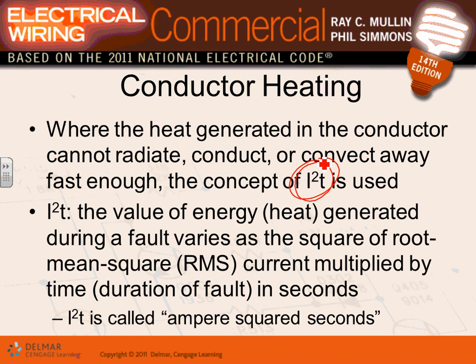It's a measurement of the heat radiated, guys, from the short circuit condition. Every time you have current going through a conductor, you have heat. But the heat coming out of 10 amps is completely different than the heat coming out of 1,000 amps, right? It's 100 times more. That's why I squared T becomes huge. If you put 10 amps into it, big deal. Let it go as long as you want. But if you put 1,000 amps into a number 14 conductor, you're going to burn your conductor because you're going to generate more heat.